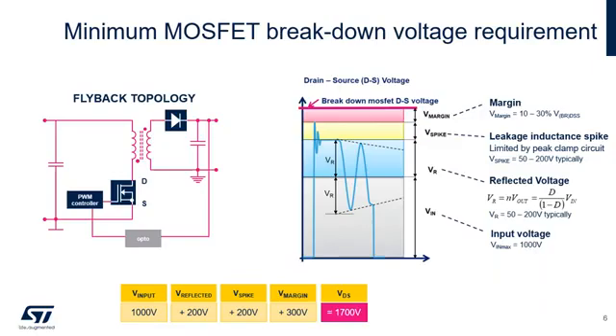First, the maximum input voltage—1000 volts in our case—plus the reflected voltage defined by the transformer turns ratio, typically 50 to 200 volts, plus the voltage spike caused by leakage inductance, also typically 50 to 200 volts, plus finally some safety margin, recommended between 10 to 30%. All of this sums to 1700 volts for safe and reliable operation in a harsh industrial environment.